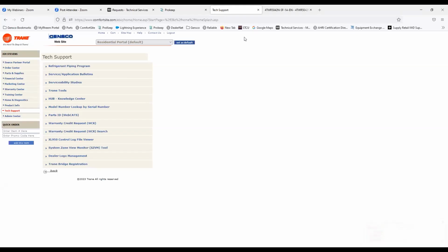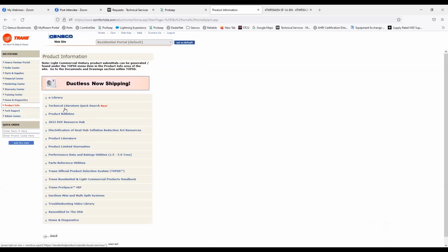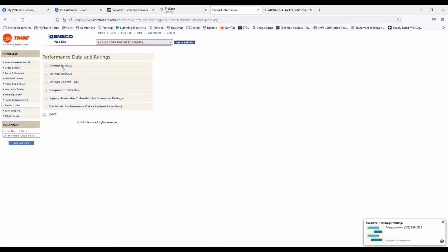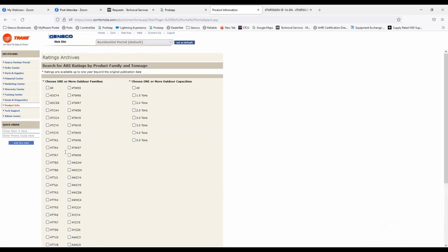Okay, now back to Comfort Site, product info, performance and utility data ratings. This is the AHRI. Current ratings or ratings archive. So right now, what's in the current ratings are the new SEER 2 ratings. So if you go to current ratings, you may not find what you have in stock at your shop. So you can go to ratings archive, go down and select your outdoor unit first.